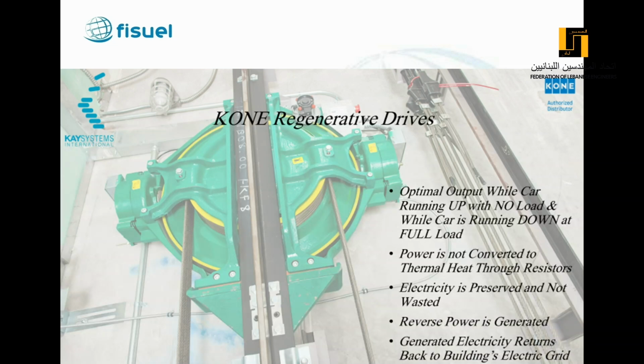motor when its synchronous speed is less than its rotor speed. In such a situation, the direction of the torque opposes the direction of the motor rotation. This happens when the elevator goes up with a light load and down with a heavy load, or in other words, when gravity is doing most of the work.